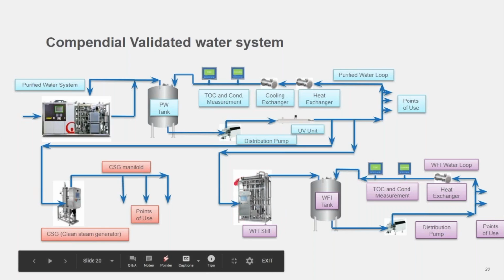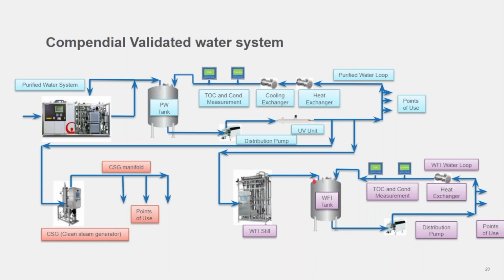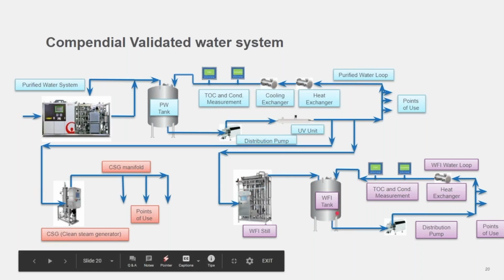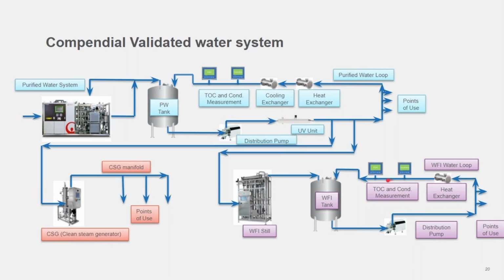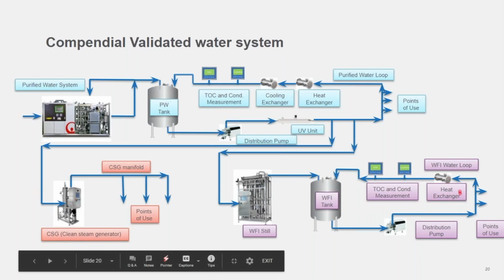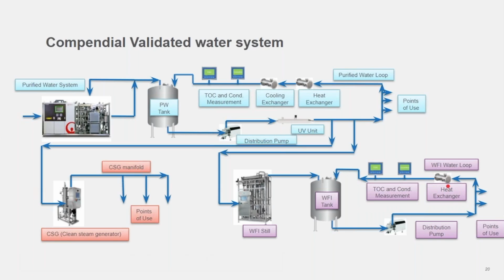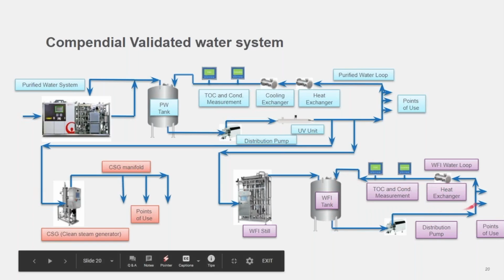This distillation shown here is a MED, a multi-effect distiller. So again, this will produce WFI water, and it'll probably produce it at a high temperature, above 80 degrees, into the WFI water tank. And then again, similar to the purified water loop, you will have a distribution loop. But typically with a distiller, the distribution loop will run hot, so you don't need any cooling exchangers. You will just have a heat exchanger on the return line, and that just keeps the water above the loop temperature you desire, typically above 80 degrees. And according to the ISPE guidelines, if we're running above 65 degrees continuously, then the system is considered to be self-sanitizing. So this is the complete compendial water system on site.